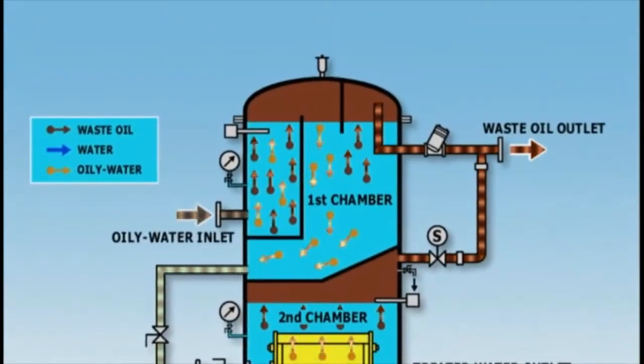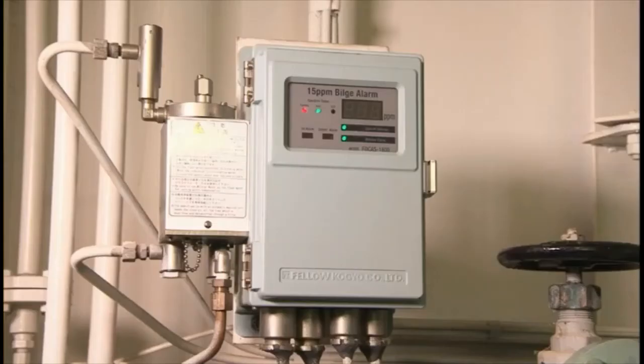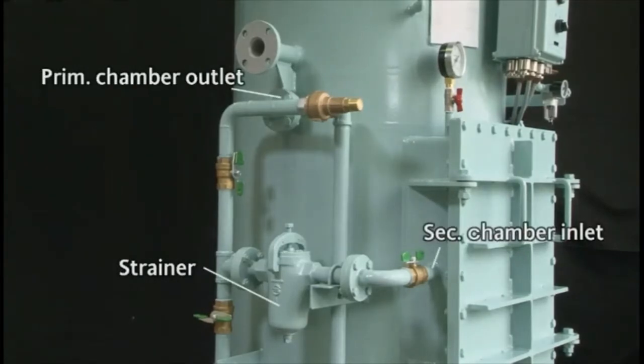Oil separated in the primary and secondary chambers collects in the upper part of the respective chambers. After the oil level of each chamber has been determined by a capacitive sensing detector, a solenoid valve is opened and oil is discharged automatically using the chamber's internal pressure. If your bilge separator is equipped with a 15 ppm bilge alarm, check the alarm in accordance with the operating manual to confirm that it works properly. After finishing bilge separator operation, clean the strainer installed in the connecting pipe between the primary and secondary chambers, to prevent the coalescer from becoming clogged with refuse and sludge.